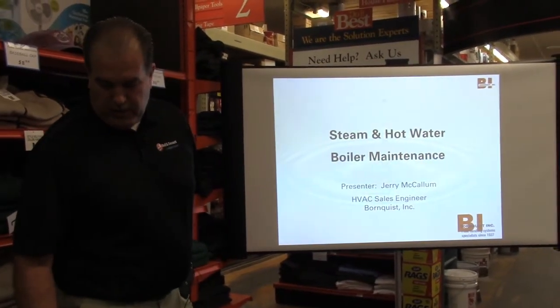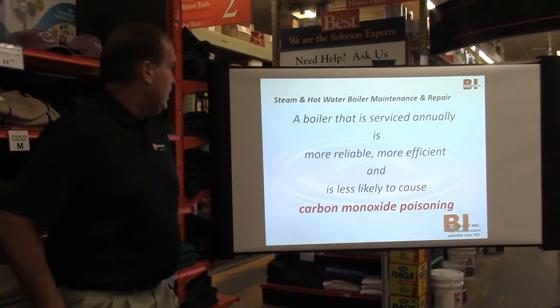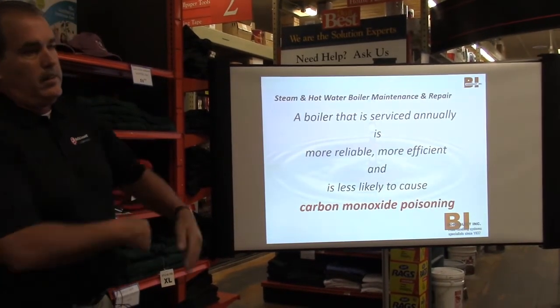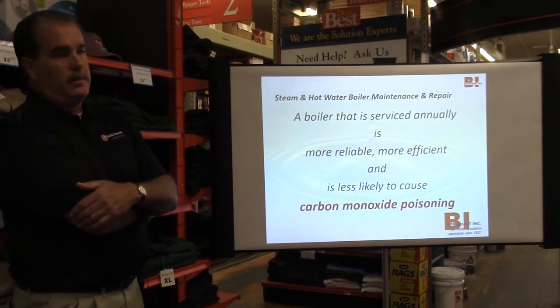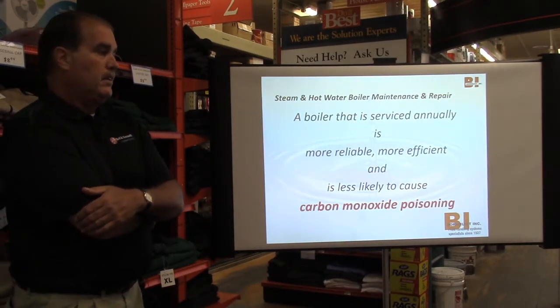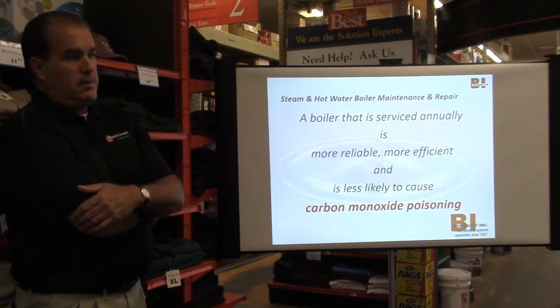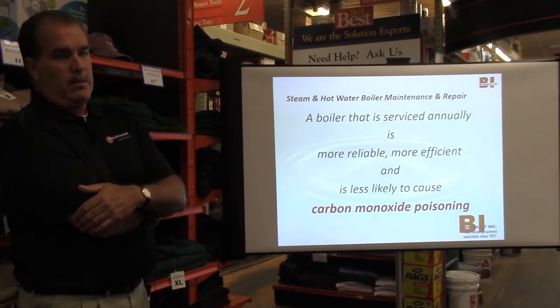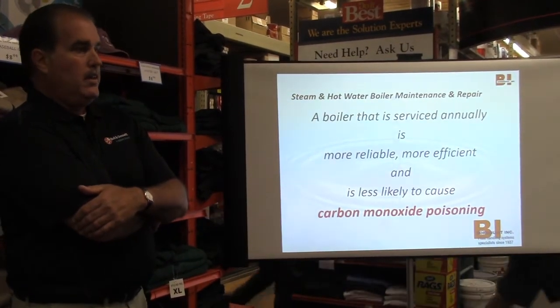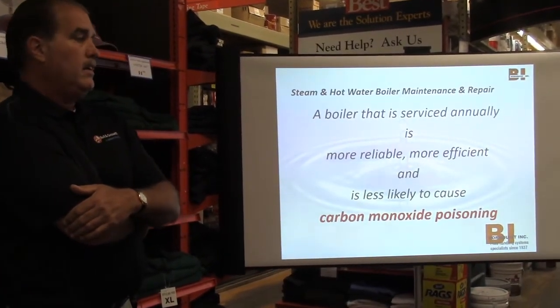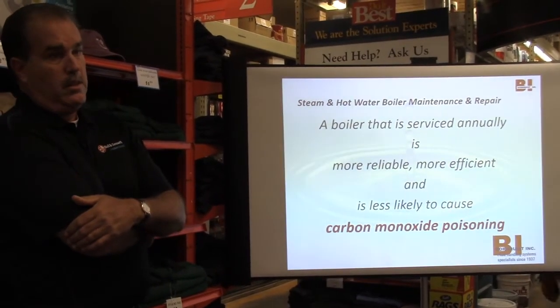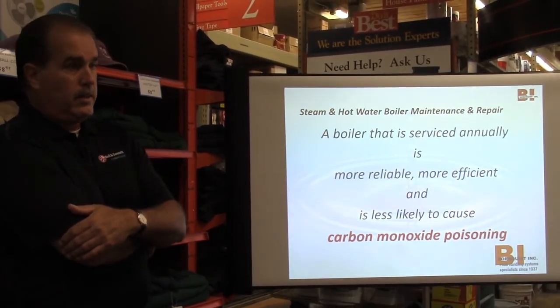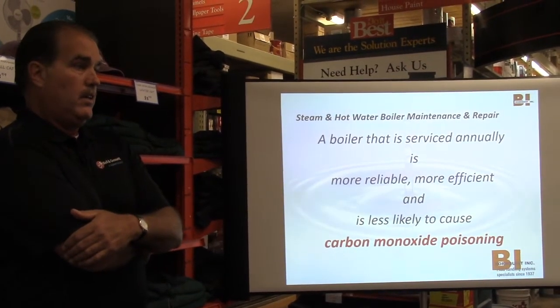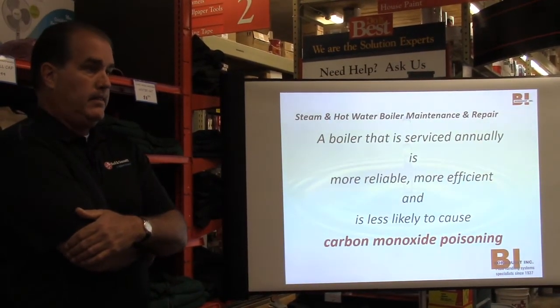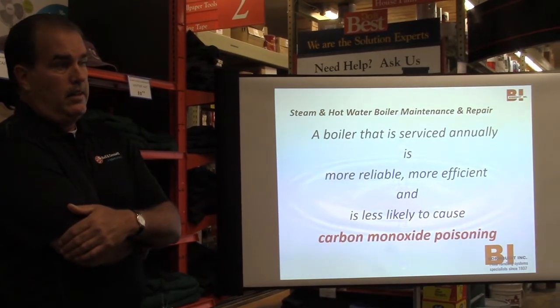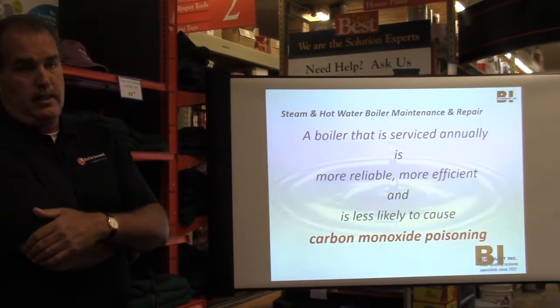So we'll get started here. One of the things we first want to talk about, obviously, is that a boiler, you have to service it periodically if you want to keep it running properly. And we do it for many reasons. Sometimes it's for internal reasons where we want to treat the water, make sure the water is good, and make sure the controls are working properly. There's ways of testing the controls, the safety devices that are on there, the operating controls and all that, to make sure they're working good. And then there's the flame side, where the burner is. And we want to make sure that's maintained and looked at annually.